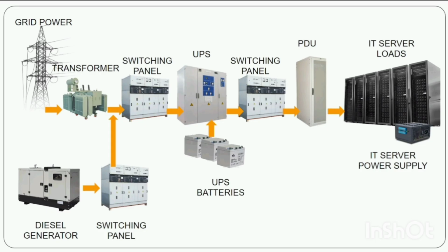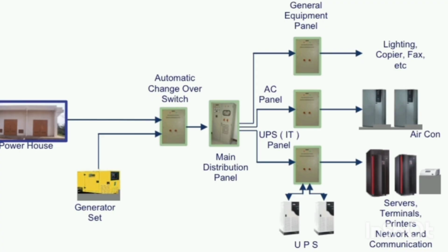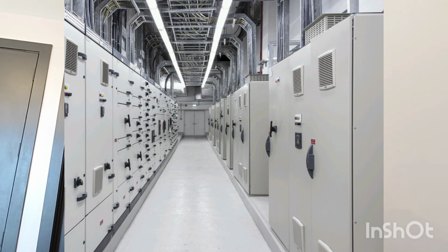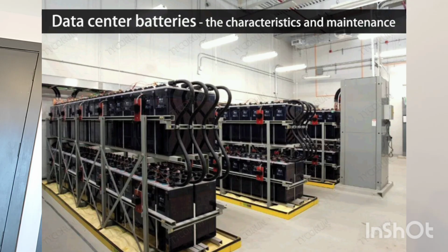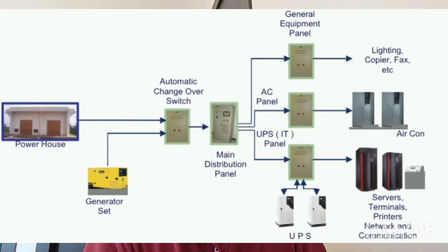But what happens if there's a loss of power? Something goes wrong with the power circuit, something trips. So we need to have backup. A generator is a backup which can run the data center until the power utility company fixes their problems. In the meantime, from the point of loss of power to the time the generator starts, something should keep the systems and the servers running. That's where the UPS comes in. The UPS keeps the servers running for a short duration, until the generators kick in and take over, until the power is restored to normal from the utility company.